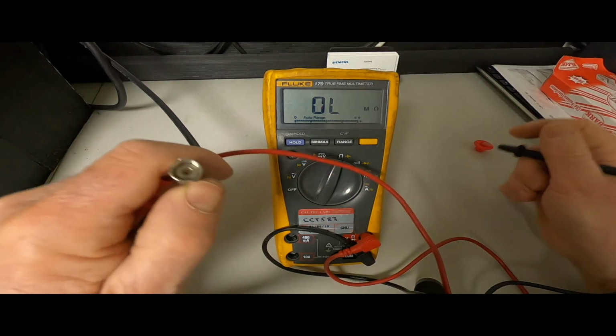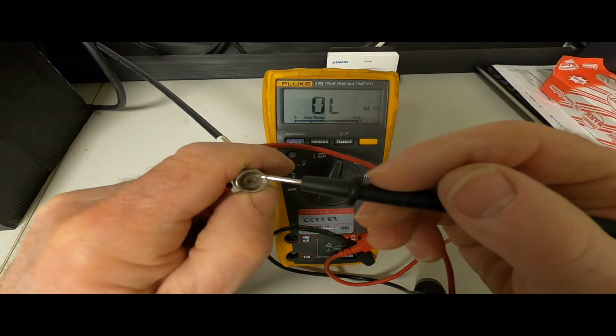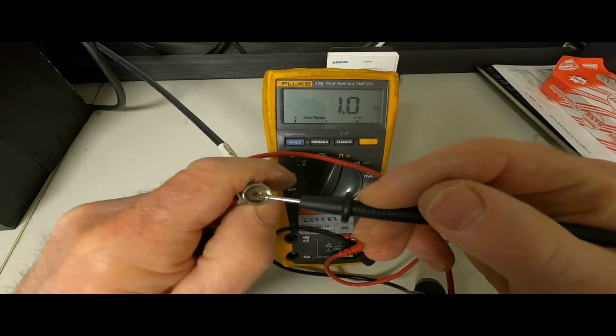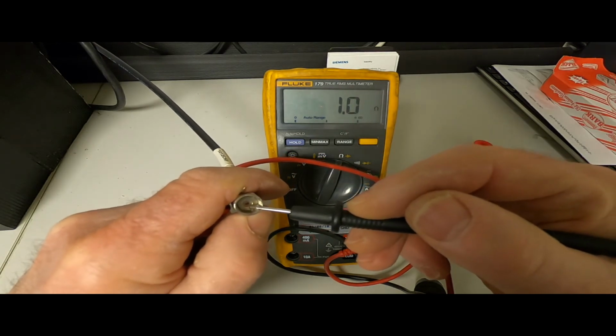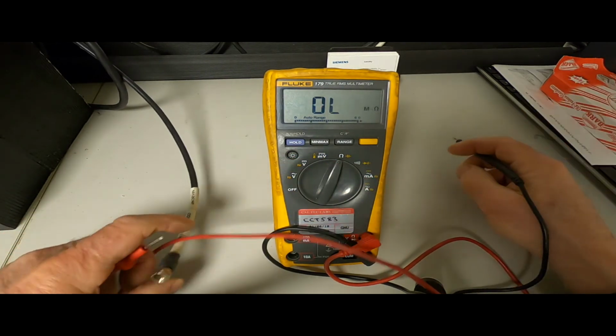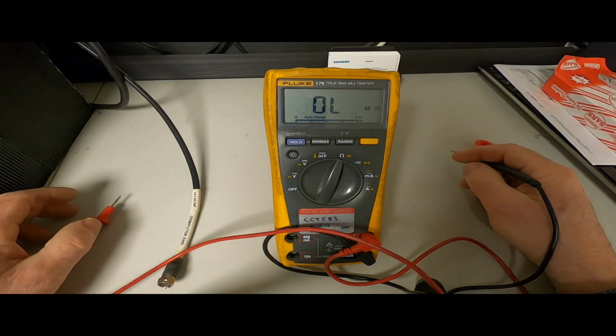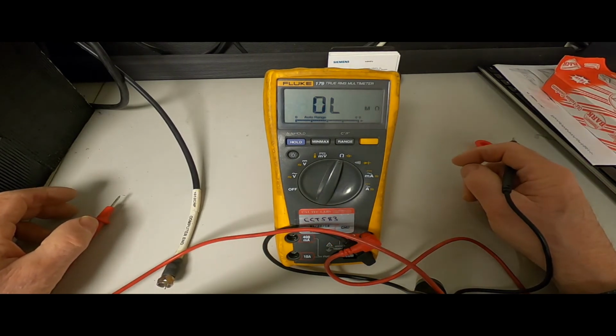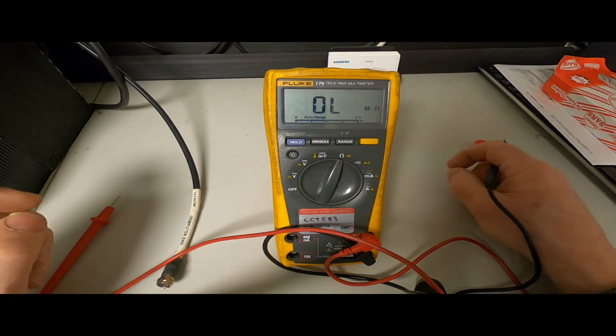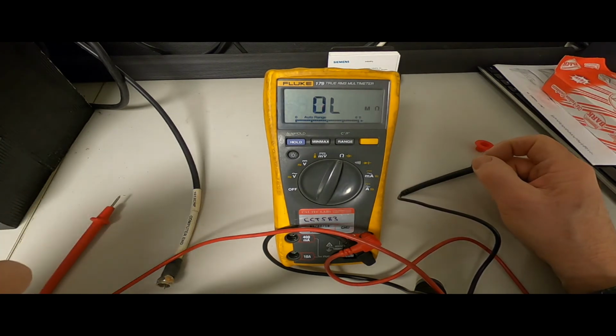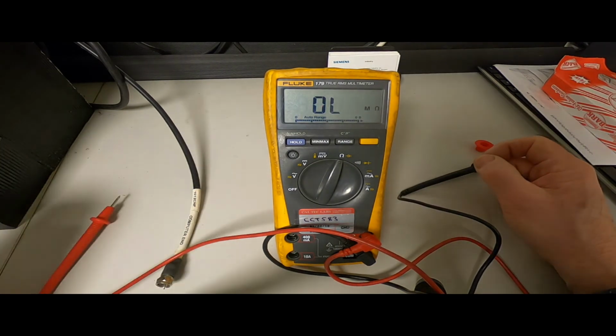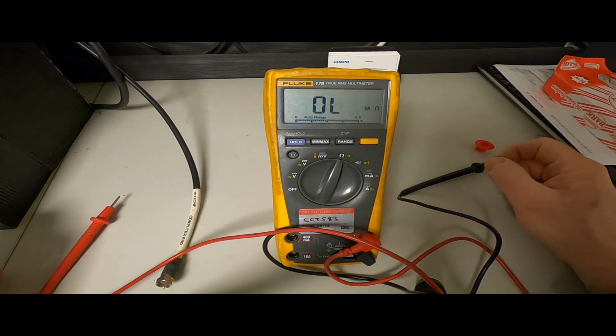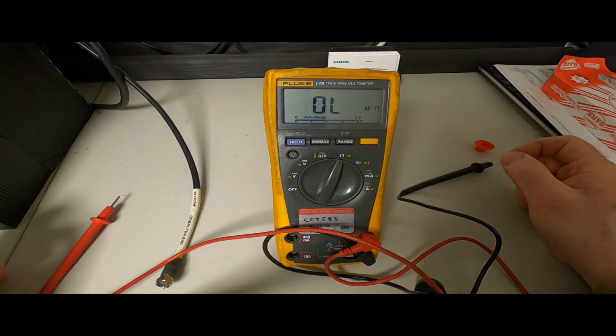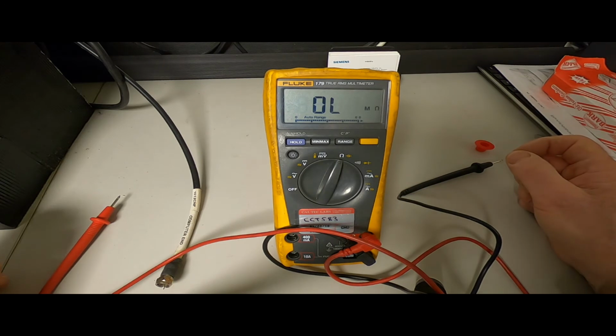Here's a situation where the cable is actually shorted. So you can see we're reading 1 ohm, which is incorrect. That may likely be that when you terminated the cables on the flow meter end, a stray piece of the shielding got wrapped around the center conductor of the cable and is creating a short. So you'd want to go to the transducer end of the cable and inspect the connection.